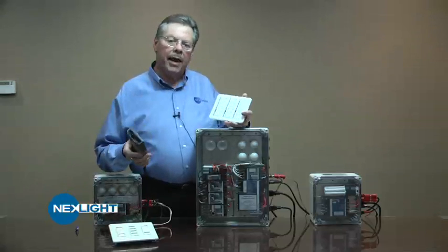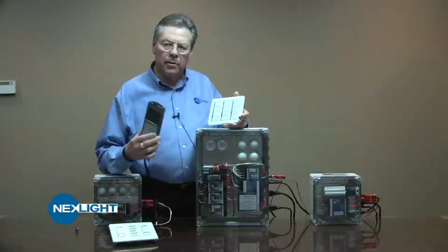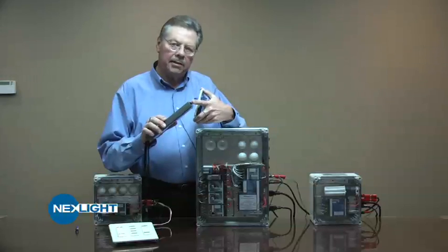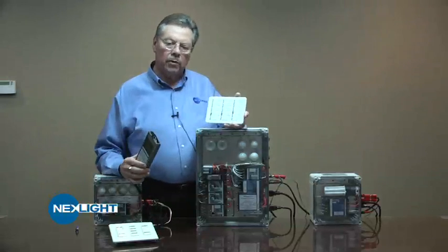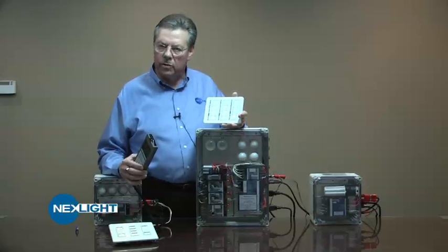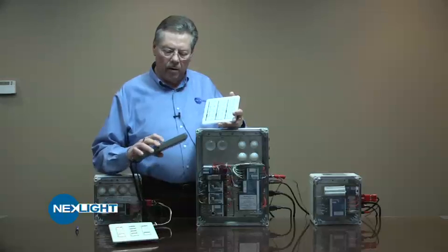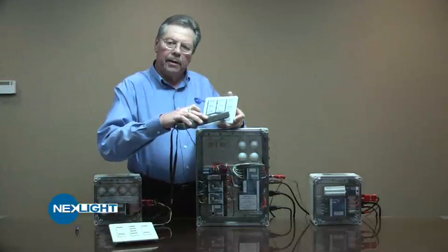And let's demonstrate what happens when we don't do it properly, because you've seen me actually read out 2 switches and we get the long tone. What happens if we don't line up the PIR sensor, the viewing sensor here, with the actual window properly, and it can't talk to the switch? So we want to read and see what this switch is actually programmed to do right now. Let's line this up and actually not get it lined up properly.